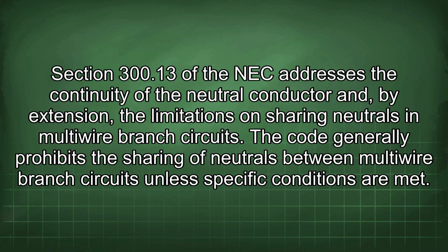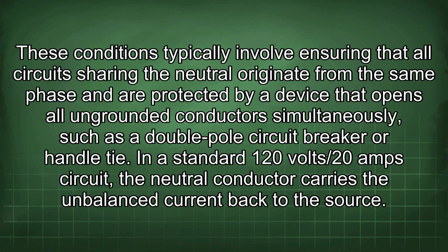Section 300.13 of the NEC addresses the continuity of the neutral conductor and, by extension, the limitations on sharing neutrals in multiwire branch circuits. The code generally prohibits the sharing of neutrals between multiwire branch circuits unless specific conditions are met. These conditions typically involve ensuring that all circuits sharing the neutral originate from the same phase and are protected by a device that opens all ungrounded conductors simultaneously, such as a double-pole circuit breaker or handle tie.